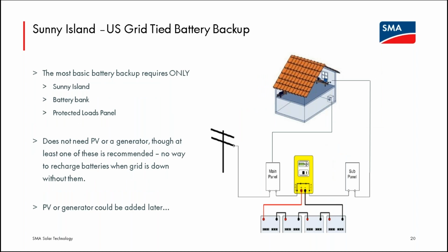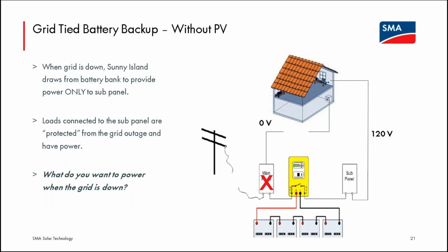So lots of people would use a battery backup system to allow the PV to continue working, but they don't even need the PV to have the system work. The simplest setup would be a Sunny Island, a battery bank, providing power should the grid fail. So this Sunny Island is sitting there watching the grid. Whenever the grid fails, the isolation relay will open. The panel behind it will get, now if we're showing a single Sunny Island, 120 volt, 60 hertz power. But in this scenario, there's no way for the batteries to be recharged when the grid is gone.